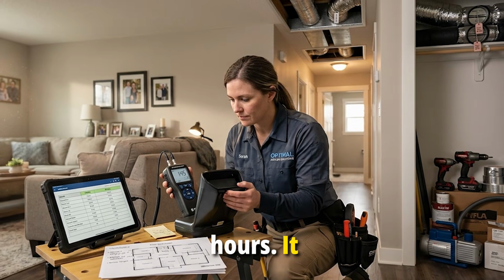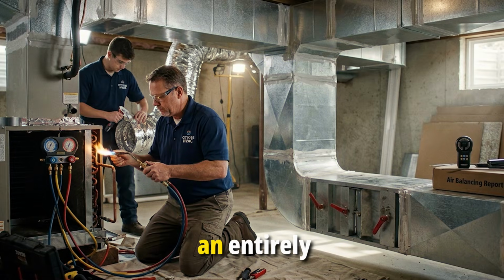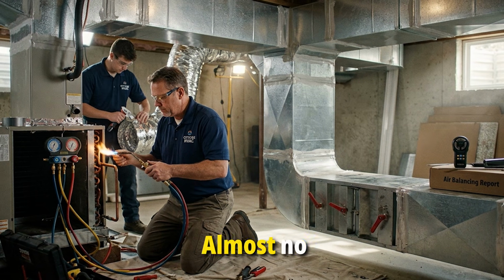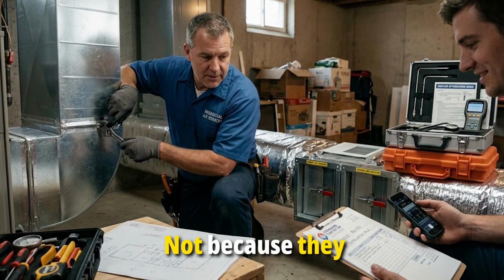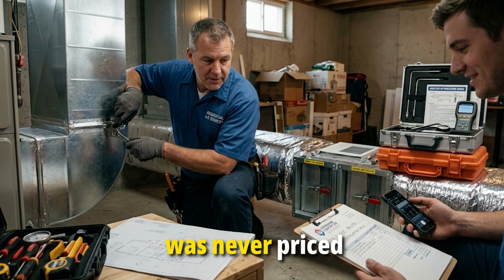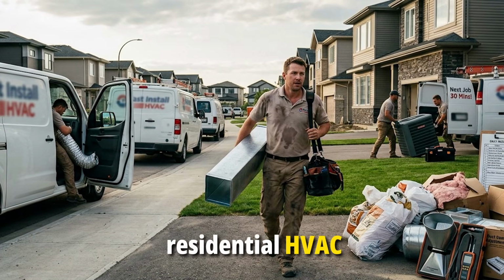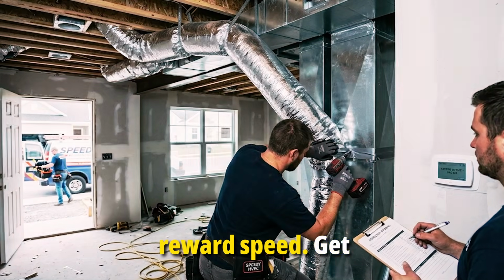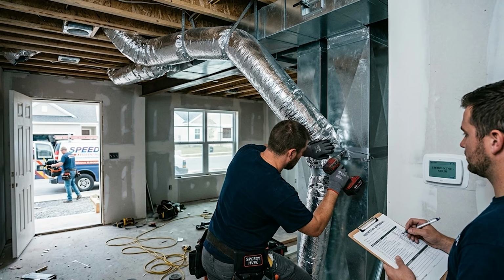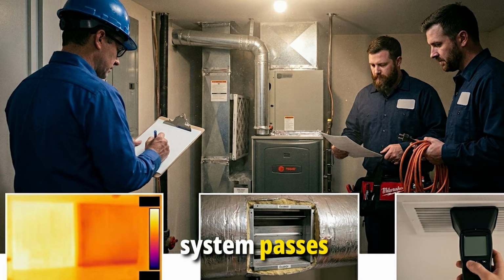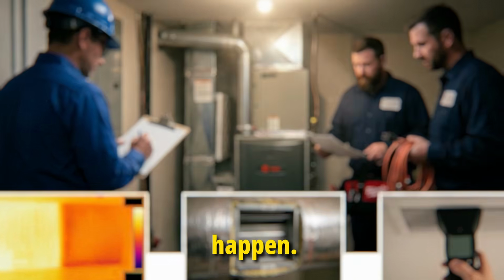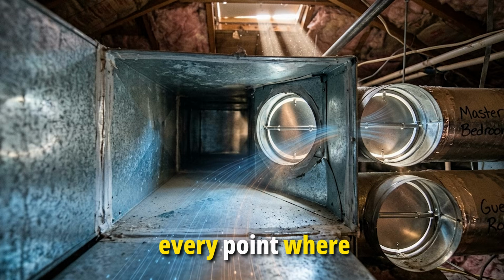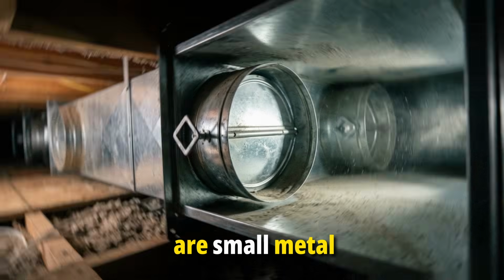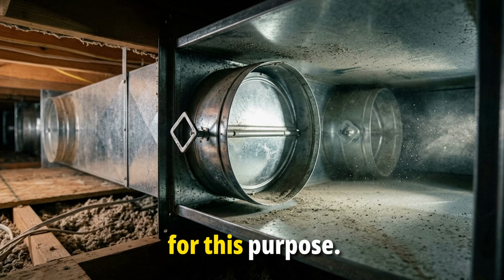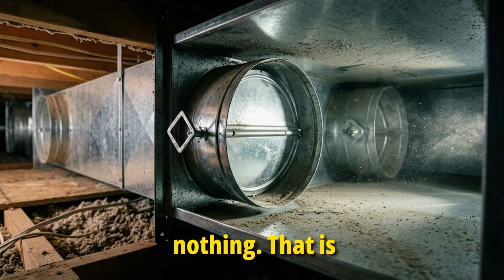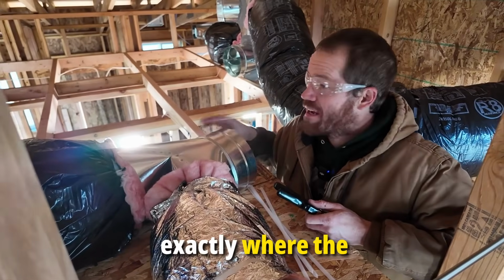It takes 2 to 4 hours. It requires specialized tools, and it is an entirely separate skill from installation. Almost no residential HVAC contractor does it. Not because they are bad at their jobs, because it was never priced into the job to begin with. The incentive structure in residential HVAC rewards speed. Get in, get the system running, pass inspection, move on. Balancing does not affect whether the system passes inspection, so it does not happen. And sitting inside your ductwork, at every point where a branch splits off from the main trunk line, there are small metal dampers that were installed specifically for this purpose, waiting, fully open, doing nothing. That is where the problem starts, and that is exactly where the fix is.